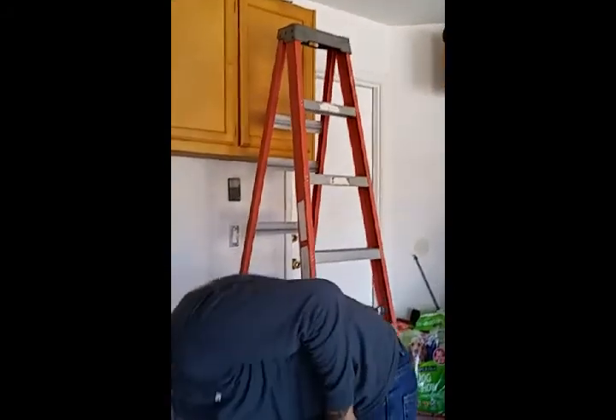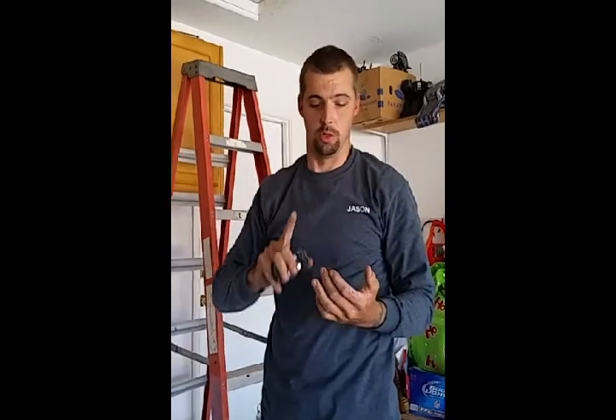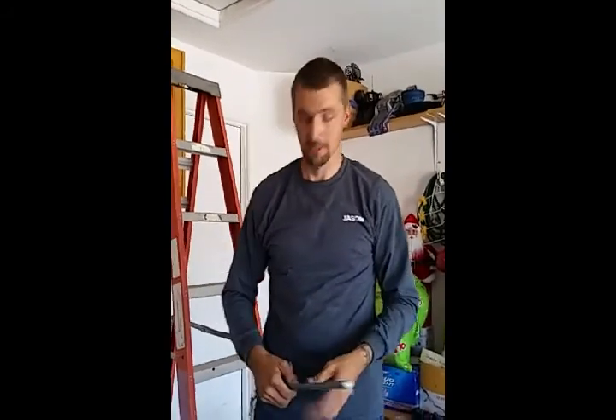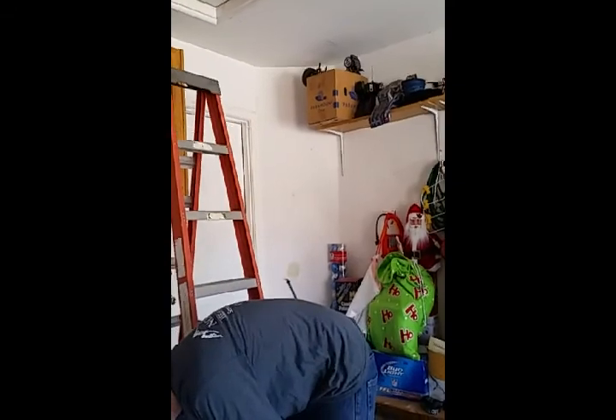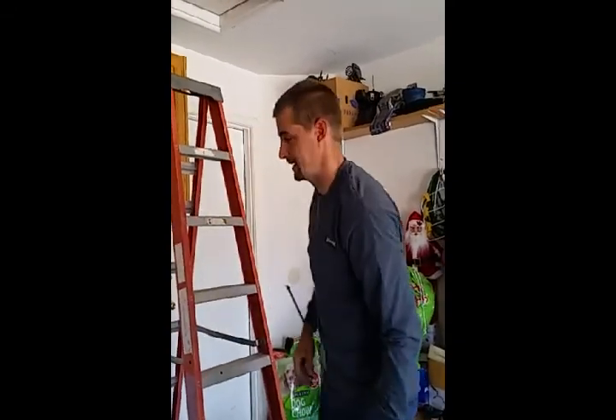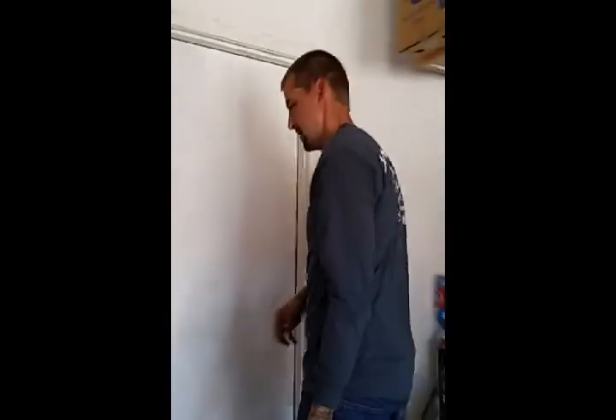Now again, I want to kind of inform you of the different aspects of what entails a checkup, an actual inspection, and then there is a tune-up. Usually the tune-ups include 1 to 2 pounds of Freon, condenser coil cleanings, things like that. I do a system checkup, and then I inform the customer of what is acting up, if anything, in their system after all of it is done, and then they make the decision to either replace it or not. So again, it's just a system checkup. It is not a system tune-up by no means. The tune-up will come after the customer has authorized any repairs that I find.